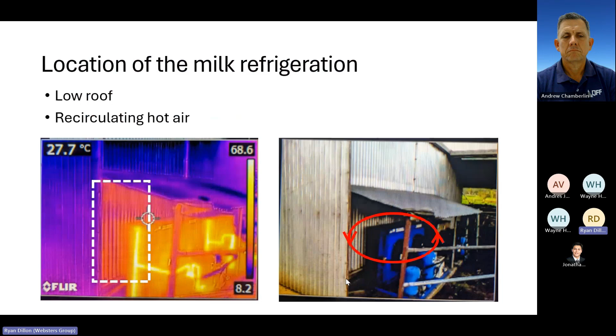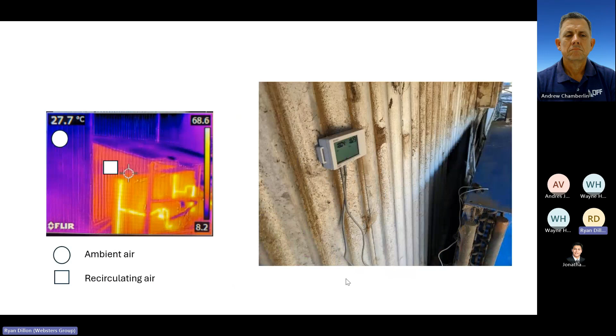Well, we put a digital temperature logger with a 1 second interval, and it's calibrated. It's about $400 as a sensor, so it's a precision instrument. And we monitored just 2 feet apart the ambient air, and then the recirculating air, just in the square on the picture on the left, to give you an indication of where we put the 2 sensors. And comparing the temperature of the air that gets sucked into the condenser versus the ambient air, what we're seeing is a difference of above 10 degrees Celsius when the milking's occurring.